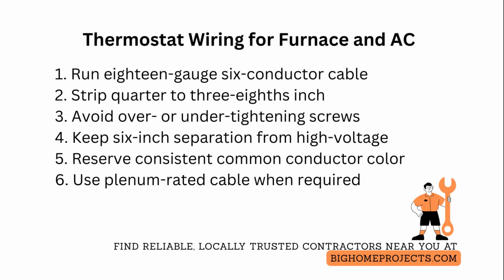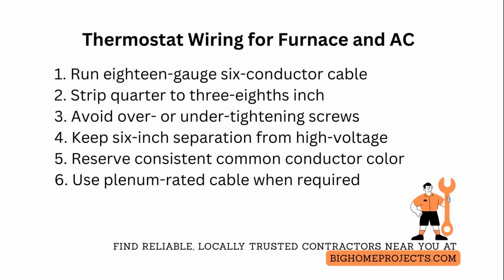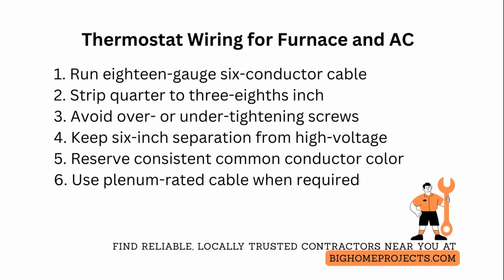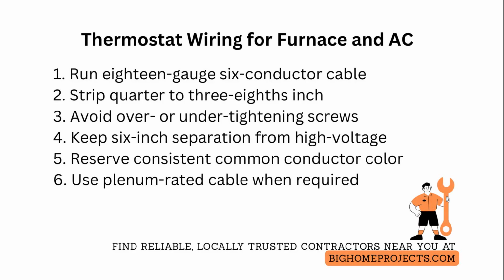Use plenum-rated cable if the run goes through return air plenums to meet code and avoid costly rework. When connecting to smart thermostats, confirm that the stat's power needs match the furnace control board's ability to supply a charging current, and if not, install a common wire adapter or a powered 5-volt or 24-volt auxiliary supply as specified.